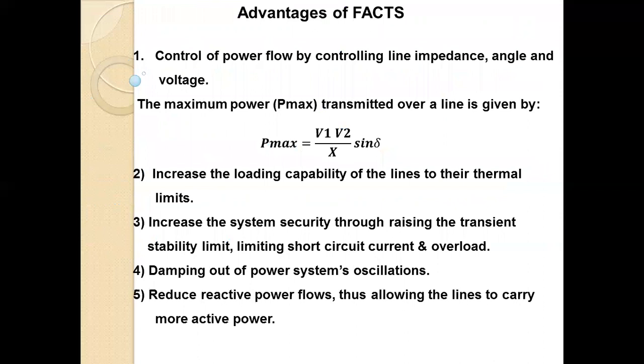Now we discuss the advantages of FACTS. The first advantage is control of power flow by controlling the line impedance, angle, and voltage. The maximum power transmitted over a line is given by P max equals V1 into V2 divided by X into sine delta. In this equation, V1 is the sending end voltage, V2 is the receiving end voltage, X is the reactance, and delta is the angle. After installation of a transmission line, we cannot change the resistance of the line, but we can easily change the reactance of the transmission line with the help of FACTS devices.